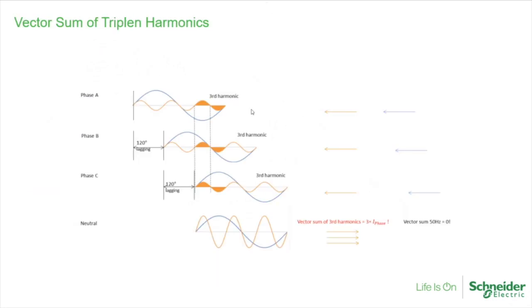And then triplen harmonics are your third, sixth, ninth, 12th. They're a multiple of 3 of your fundamental. And these have a unique effect in that they sum in the neutral. So if you have a lot of triplen harmonics, you can wind up with current on your neutral or ground, which isn't ideal.